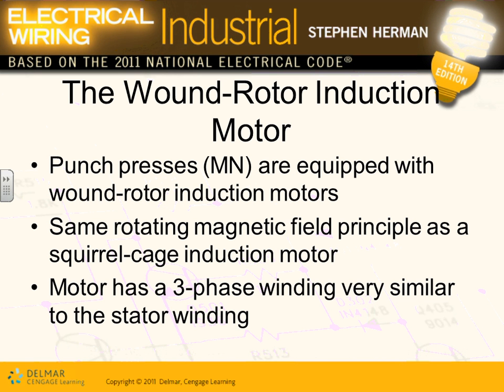The other motors, guys, wound rotor motor. Wound rotor induction motor. These guys, the rotor itself has some coils inside it. That's it. That's the only difference. Coils inside it. So you have to have brushes and so forth. The advantage of this one, Jeff, the wound rotor motor, is they have huge torque. They are really good horses. So if you have punching, like punch presses and so forth, they need a lot of torque to make holes. They use a wound rotor induction motor.